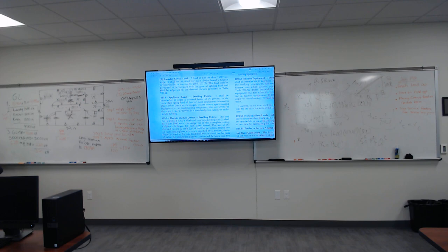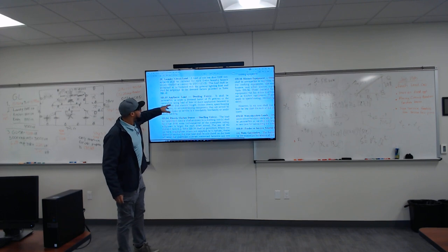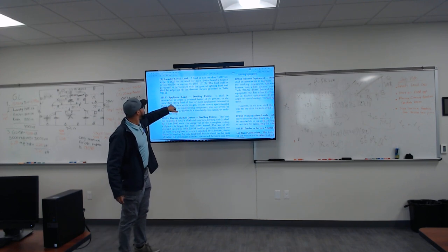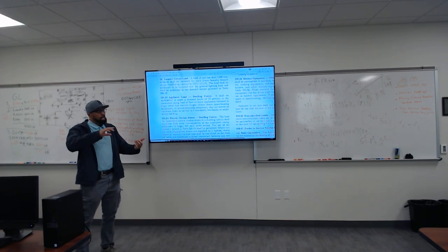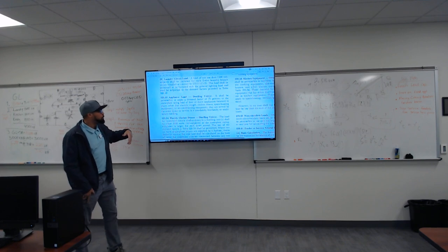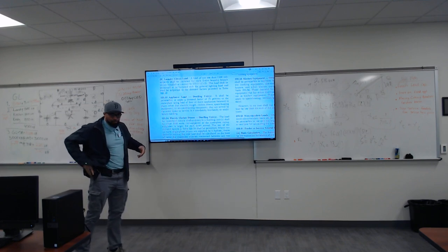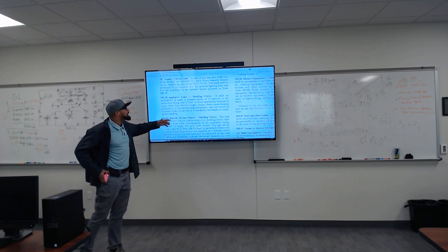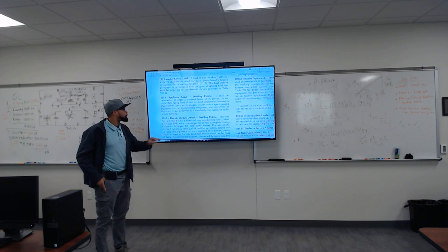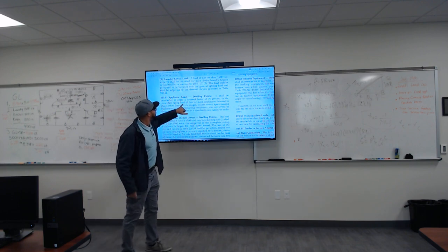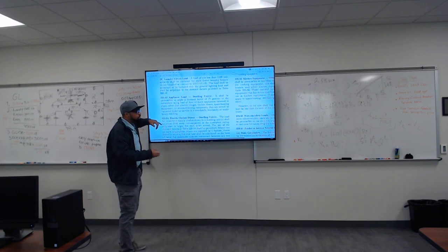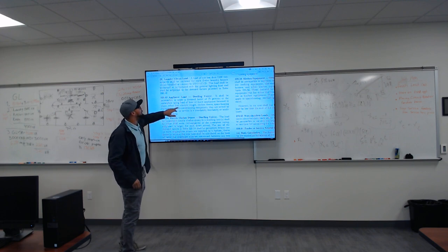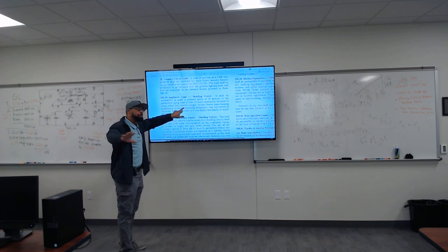All right, let me break that down in layman's terms. It's saying anything that is fixed. It shall be permissible to apply a demand factor of 75%. The reason I got 75% is because you're not gonna be using a dishwasher or fixed appliances at a full capacity of 100%. So 75%, this is for load calculation purposes, to the nameplate rating load of the four or more appliances fastened in place, like a microwave, refrigerator, toaster oven, etc. But not a stove. An electric range, gentlemen, is a stove.